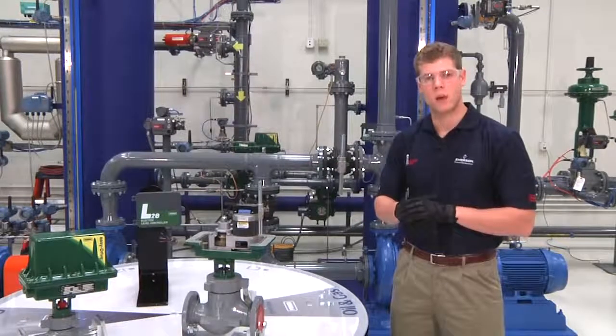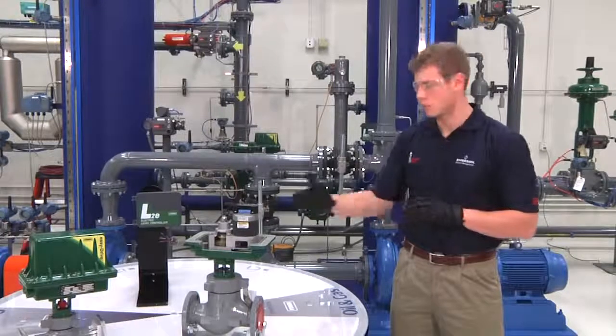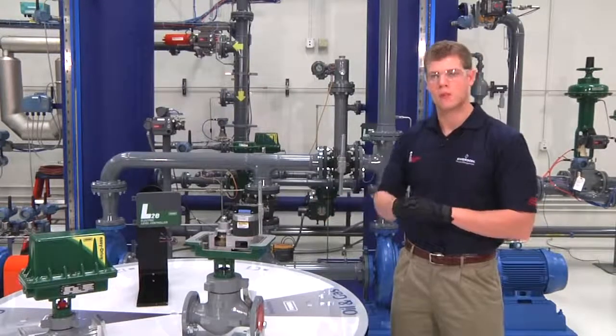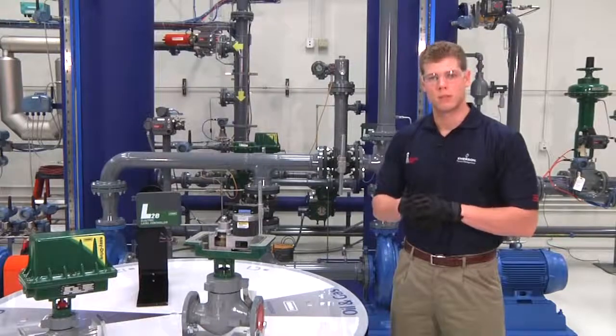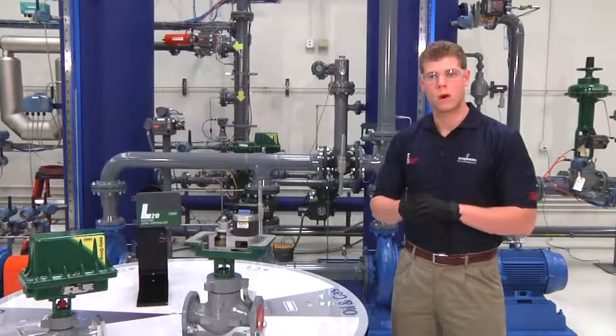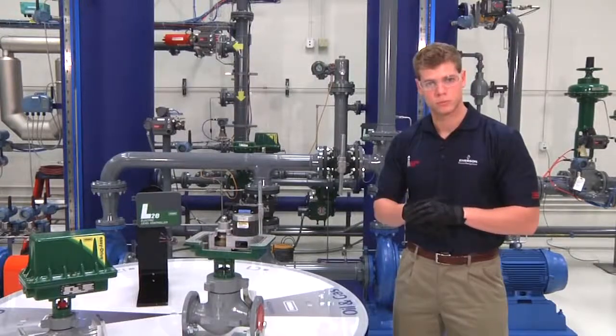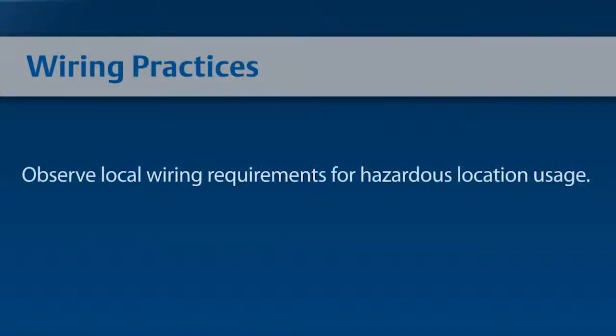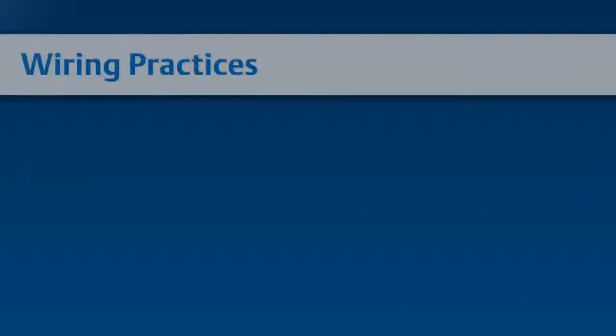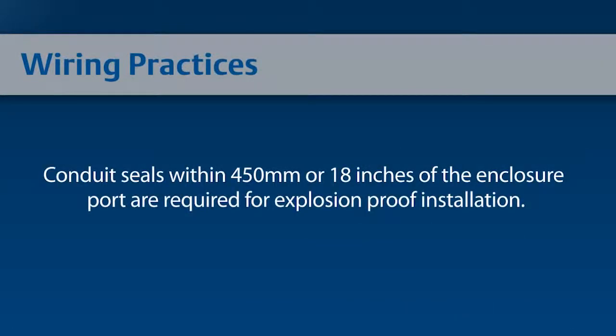We will now connect the wiring to the terminals within the Easy Drive on the D4 assembly. For safety purposes, make sure that none of your wires are live during this procedure. Some other wiring practices to follow include: observe local wiring requirements for hazardous location usage. Conduit seals within 450 millimeters or 18 inches of the enclosure port are required for explosion-proof installation.